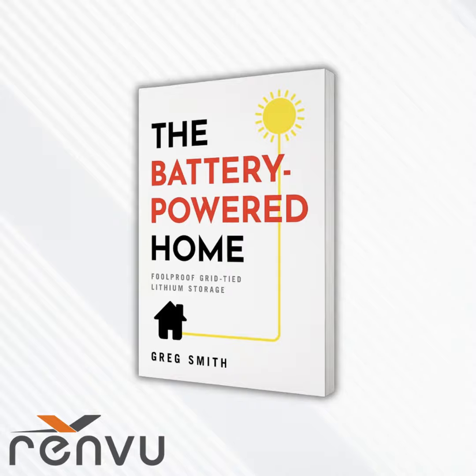The answer, like for most things in this industry, is two words: it depends. For Tigo's solution, it's closed loop - a fancy way of saying we don't work with anybody else except Tigo, except for the battery. If the battery is AC coupled, you can use our inverter and ATS, connect the generator to the ATS, and that's fine. But you can't use our ATS with an EG4 or a Sol-Ark inverter - it won't work, because there's a communication cable between the ATS and our inverter, and they only speak that language.